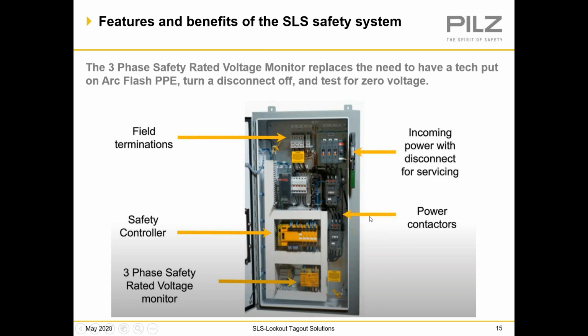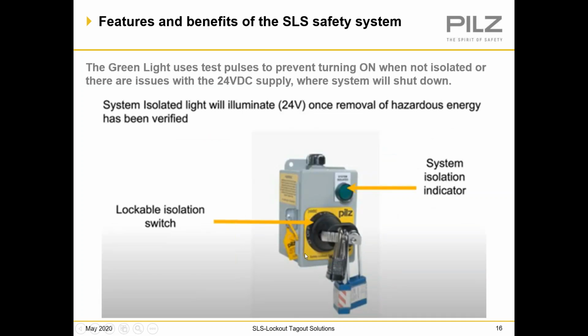You have your power contactors, which are AC23A rated, and you have a disconnect switch up here, which is disconnecting power to the panel. It is not used for lockout. This whole panel is a lockout device. The remote stations have 24 volts DC power coming in.